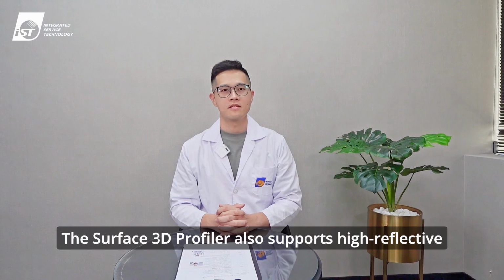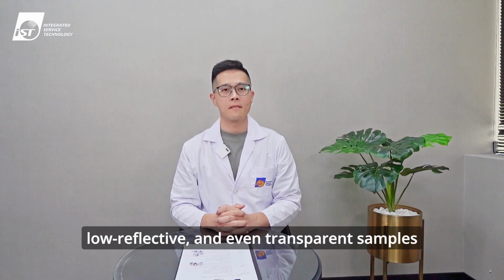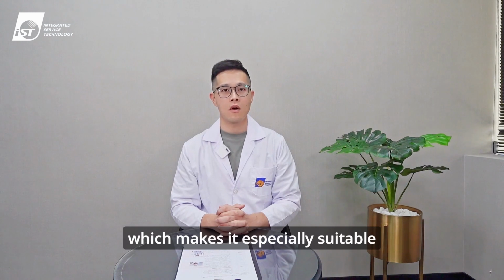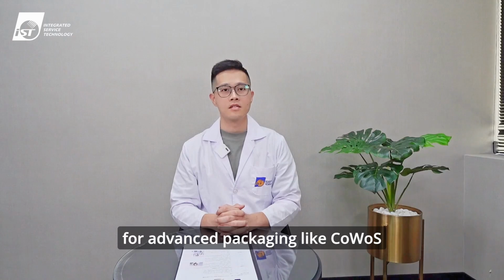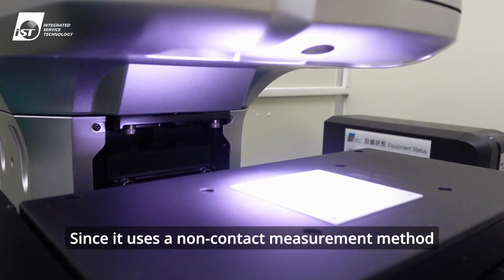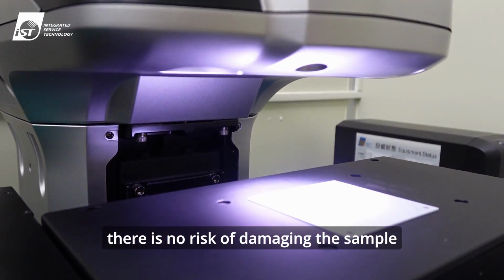The Surface 3D Profiler also supports high reflective, low reflective, and even transparent samples, which makes it especially suitable for advanced packaging like CoWoS. Since it uses a non-contact measurement method, there is no risk of damaging the sample.